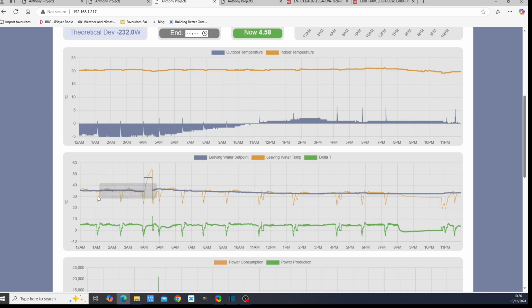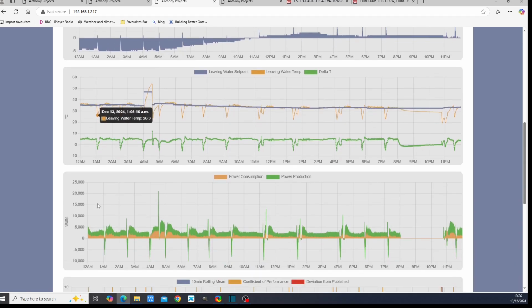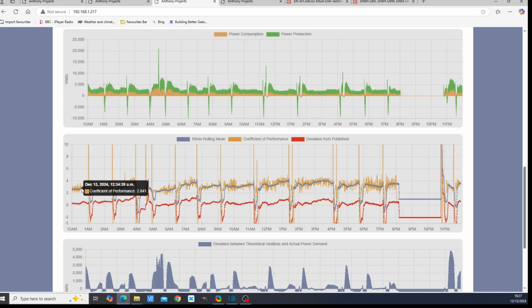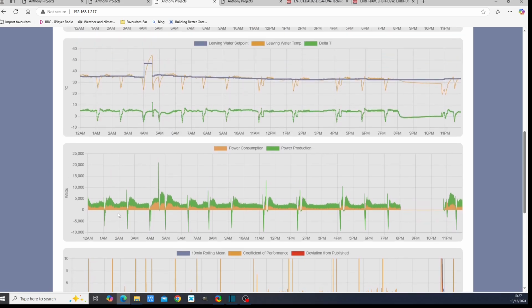It will dump your leaving water temperature, and then you'll see you're losing heat. The heat transfer is going from your heating medium back into your refrigerant, and then that's used to remove the ice from the evaporator. So in this particular example, your coefficient of performance is about 2.9, which is not bad actually, but it's reduced down to about 2.5 on account of these defrost cycles. They do take a lot of energy out of the system, so it's worth bearing that in mind.